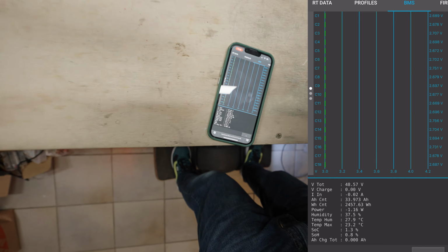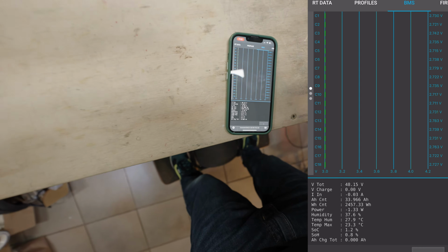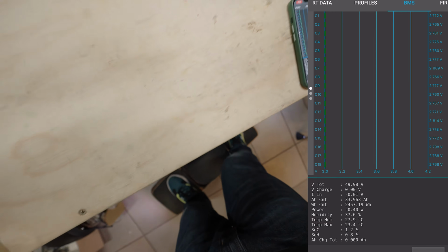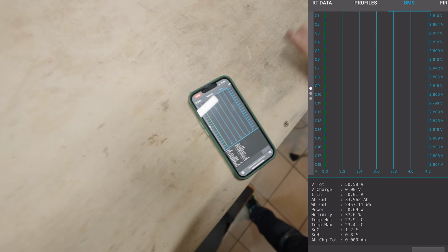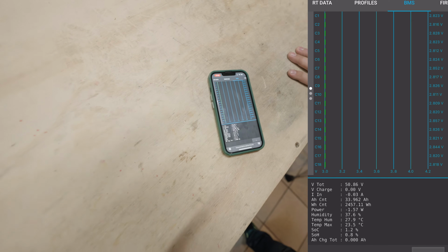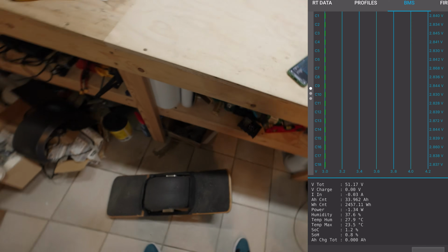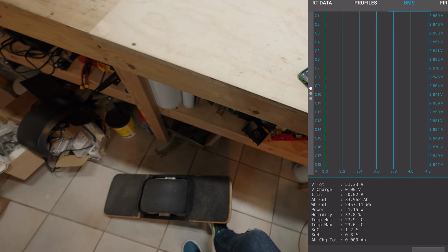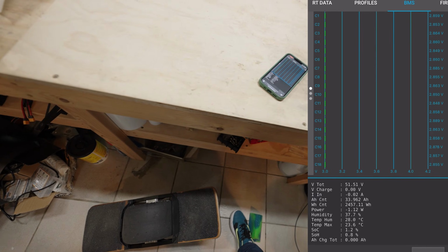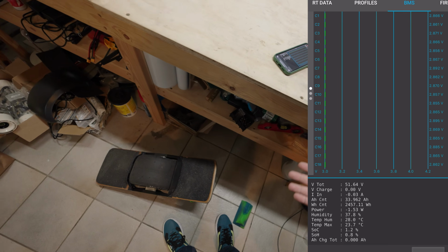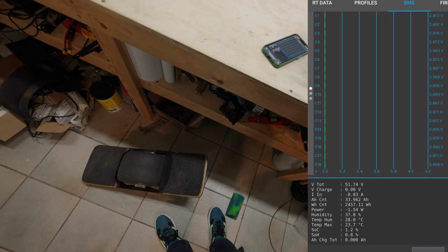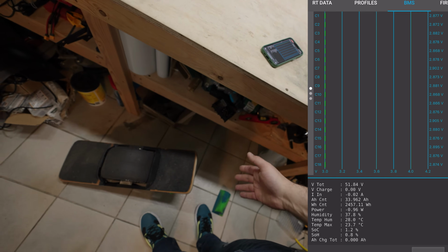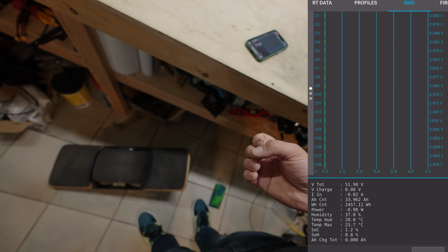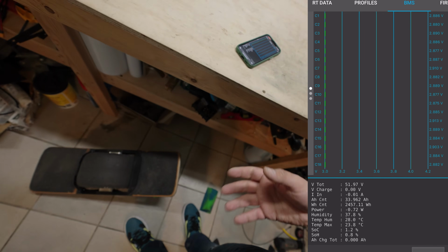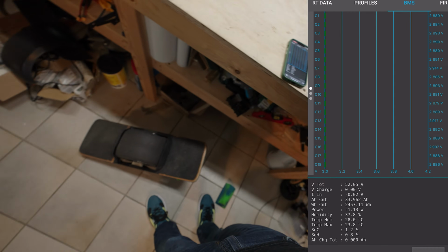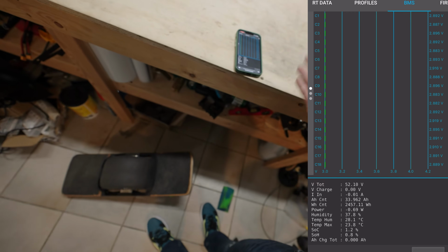But you'll see that if I let off, voltages rise back up, well above 2.5 volts per cell, and they start to settle. So any voltages you saw drop to 2.4, 2.3, 2.5-ish, those aren't the actual voltages, that's just what they are under load. Much like when you open a spigot or faucet, the pressure behind the valve drops as water flows, similarly the current flows and the electrical pressure, the voltage, begins to drop.